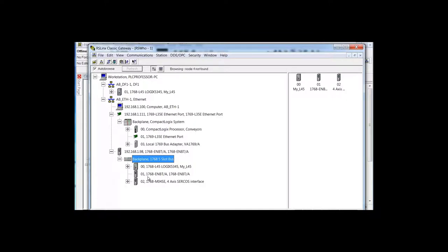The backplane is made up of backplane segments. Each module has a segment of the backplane as part of its construction. And when you assemble these modules together, like the 1769 modules, they slide in next to an adjoining module, and then there's a little lever on the top and towards the back that you rotate counterclockwise, and that engages a connector into the socket of the adjacent module to the left. With 1768, it engages into the module to the right.